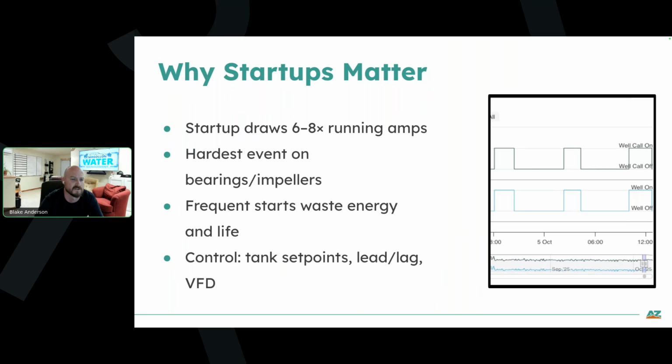You can set up your wells to run in lead and lag, so you could have your most efficient well run after the tank drops a couple feet, and then a foot lower than that, if that one's failing to keep up, you can have another one go. You can look at time of use and letting things run a little bit lower and fill up overnight. It just really is situational and depends on how your system's designed and what control changes you can make.